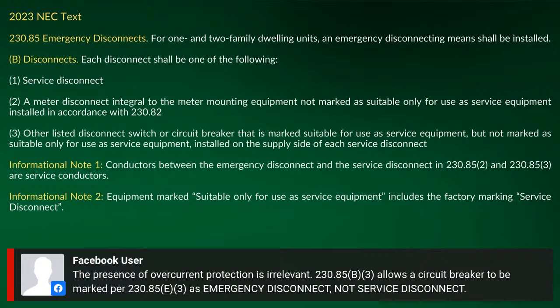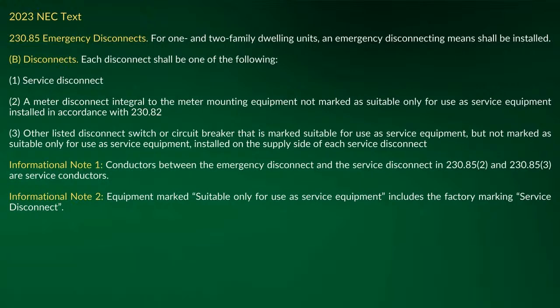I want to say this is Justin probably, but I don't know because it just says Facebook user. But since the presence of the overcurrent protection is irrelevant, 230.85(B)(3) allows the circuit breaker to be marked per 230.85(E)(3) as emergency disconnect and not service disconnect. But the whole thing there, in my opinion, is now you're going to the line side of the ATS, which is service rated, on the load side, and that's not. And James was always saying that's supply side still, but to me, it's just weird because how can I sit there and say that ATS is still supply side when it's on the load side of the emergency disconnect? That could be a circuit breaker that's main lug only.